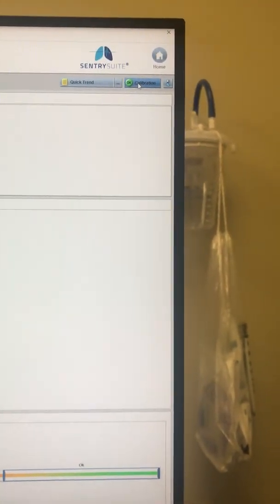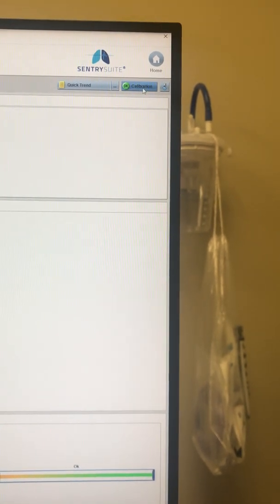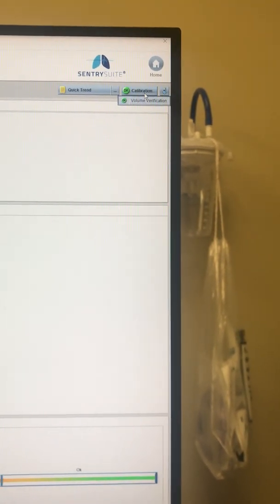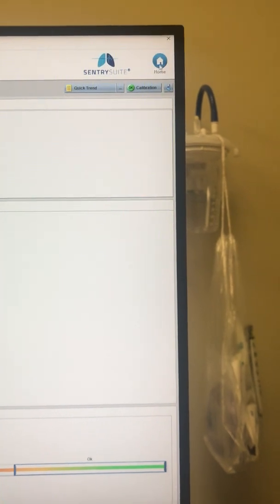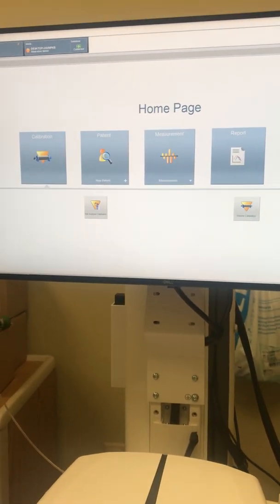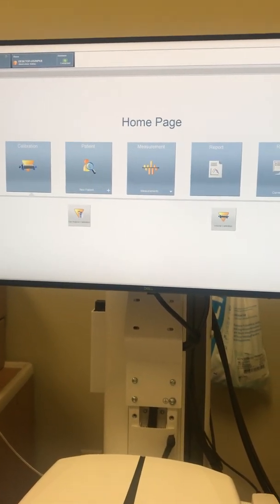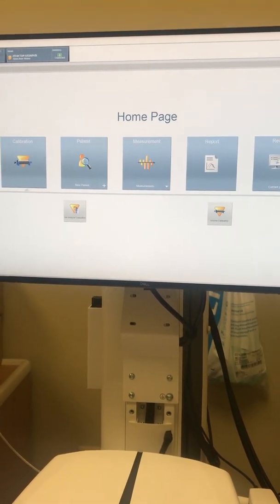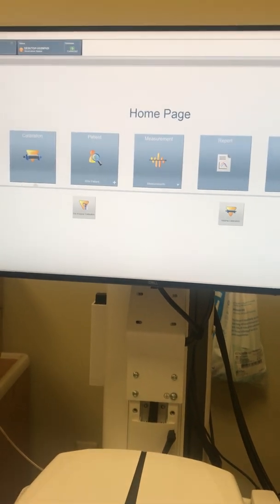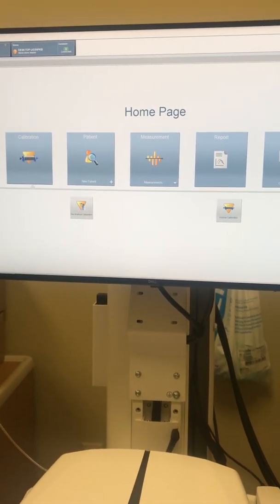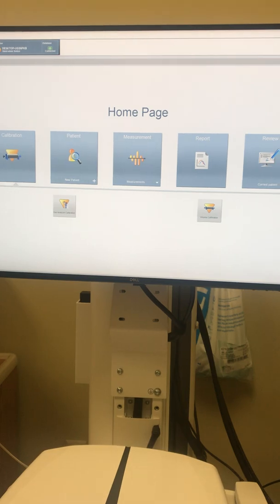So you have to calibrate every day, of course. But you can go home after that. We're not going to have to print out every day. It's a once a month thing that we'll print out. So there'll be 12 reports and we have to keep those for 2 years. So there's that part. So we got the calibration part done.